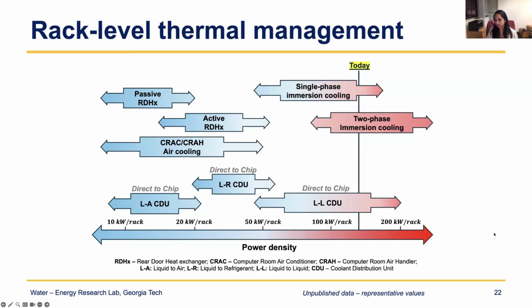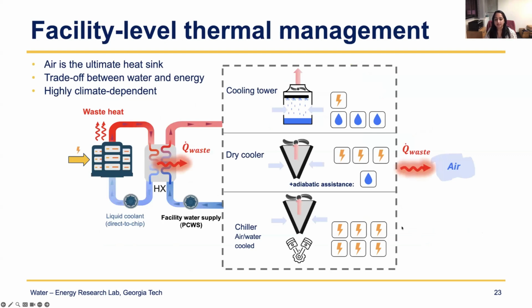We're actually in the process of extending this to a 1 megawatt rack and seeing which technologies, with what kind of flow rates and fluids, allow us to do cooling of a 1 megawatt rack without reaching erosion limits, so maximum flow rates.